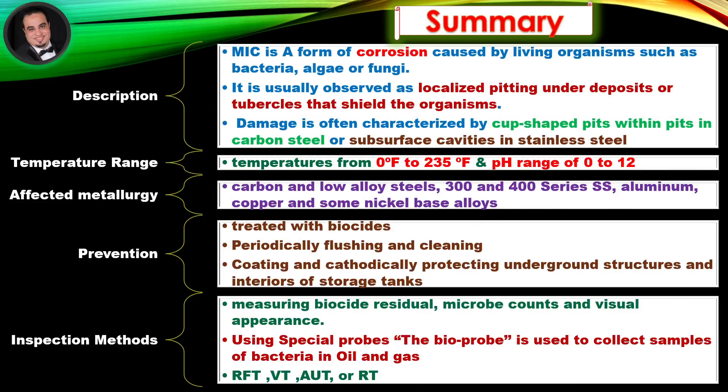Summary. Description: Microbiologically influenced corrosion is a form of corrosion caused by living organisms such as bacteria, algae, or fungi. It is usually observed as localized pitting under deposits or tubercles that shield the organisms. Damage is often characterized by cup-shaped pits within pits in carbon steel, or subsurface cavities in stainless steel.